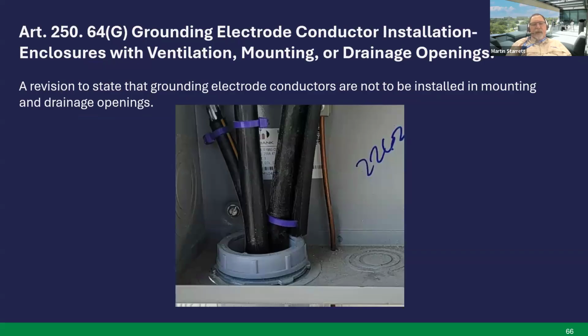Next slide. Article 250-64G, grounding electrode conductor installation, enclosures with ventilation, mounting, or drainage openings. Current code says you cannot install a grounding electrode conductor in a ventilation opening. The 2026 revision added in mounting and drainage openings. So you will not be able to do what this little picture shows right here, that drain hole. You cannot bring that grounding electrode conductor up through that drain hole, mounting holes, or ventilation holes in 2026.